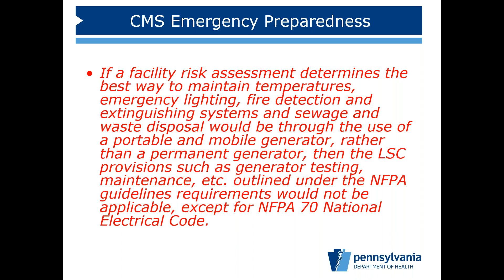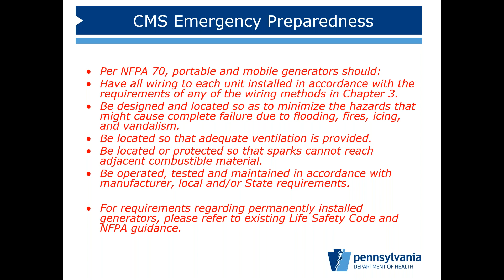Per NFPA 70, portable and mobile generators should have all wiring to each unit installed in accordance with the requirements in Chapter 3, be designed and located so you're not in an area where you'll flood or be vandalized, have adequate ventilation -- so we need to look at our HVAC systems and make sure it's not affecting the building -- and we don't want any sparks going against combustible material.